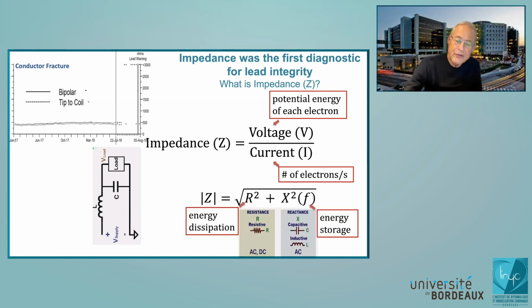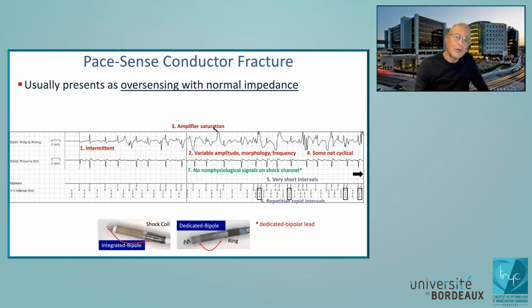And that's because impedance has two different components. But when we're just dealing with leads and the way it's measured currently, I'm going to dumb it down and say impedance relates to energy dissipated in the lead. And that part of impedance is called resistance. There's also another part of impedance that's highly relevant for alternating currents called reactance, that involves energy stored in the system. Say if you put your device in an MRI scanner, it can help store energy from the magnetic fields. And that's something we don't want to do, but we're not going to go there. That's for a more advanced course.